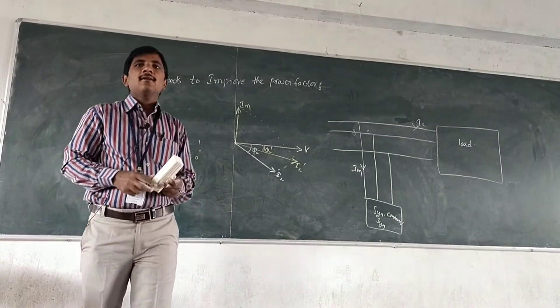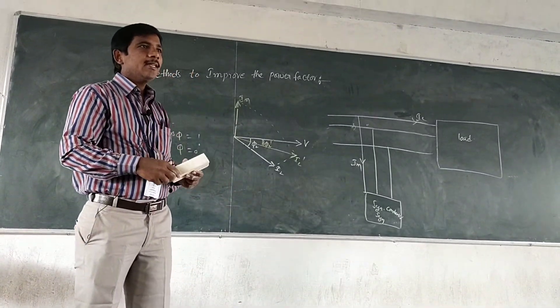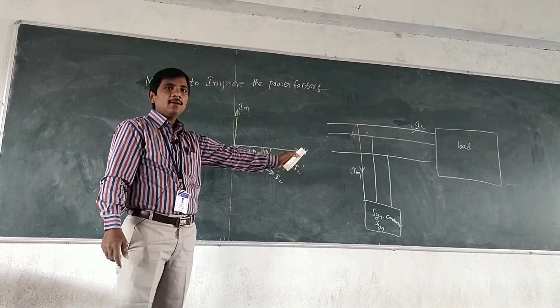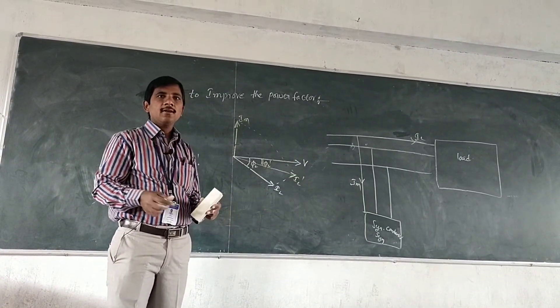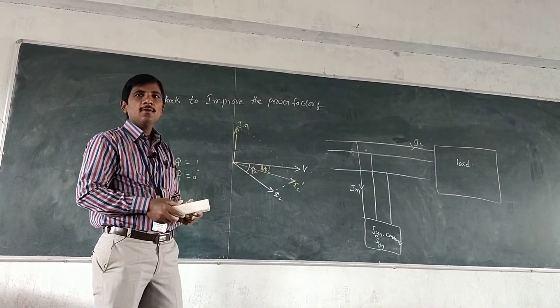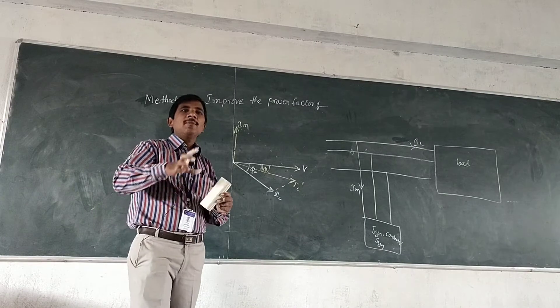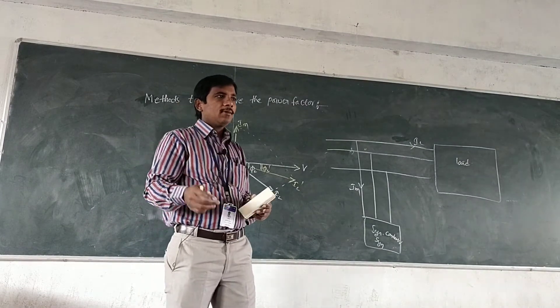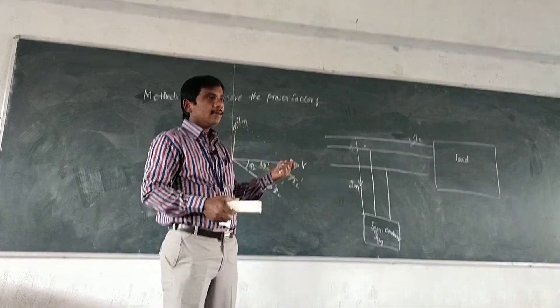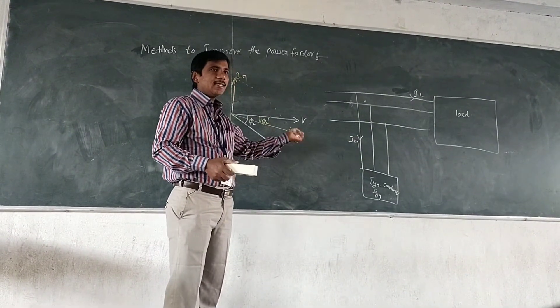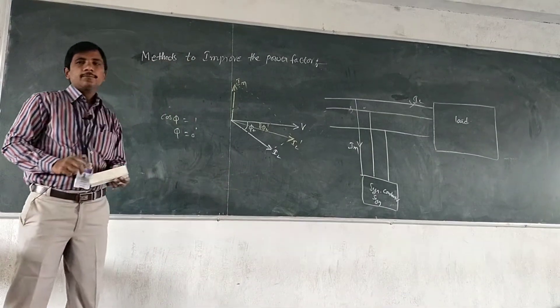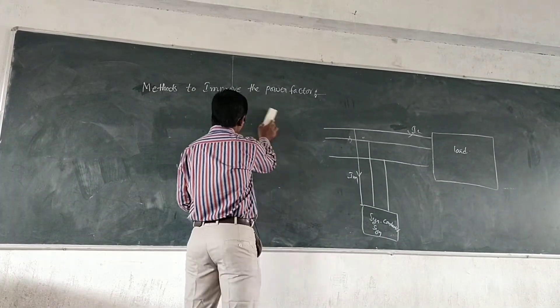The synchronous condenser is similar to a static capacitor. A synchronous motor when over-excited and running at no load acts as a static capacitor — a synchronous condenser. By increasing field excitation, the synchronous motor running without any load gives a leading current and acts as a capacitor — a synchronous condenser.